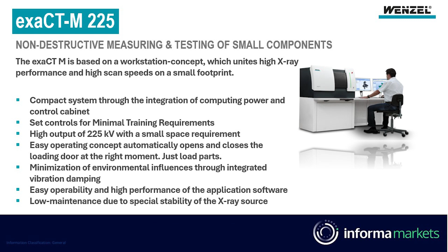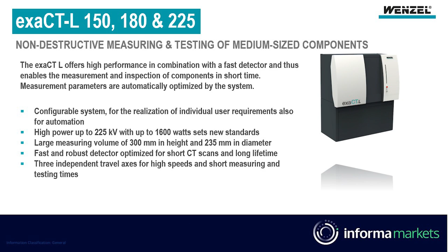A little bit more in size is our L machine. This one also uses a 225 tube, but we've recently put in a 180 kV microfocus, so the resolution in this machine can get to 5 microns throughout this whole scan envelope, which is important because you have a larger scan envelope and you can scan many parts at the same time. So this gets into the realm where, sure, you could do larger parts, but also think in the volume of the number of parts you can do with your scanner.